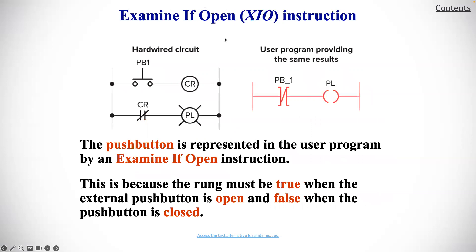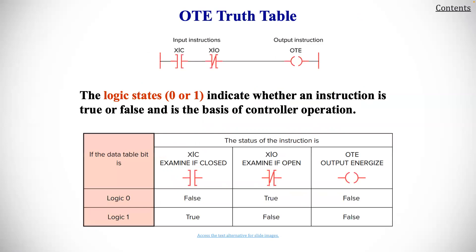For the XIO instruction, the push button is represented in the user program by the examine if open, XIO instruction. This is because the rung must be true when the external push button is open and false when the push button is closed.